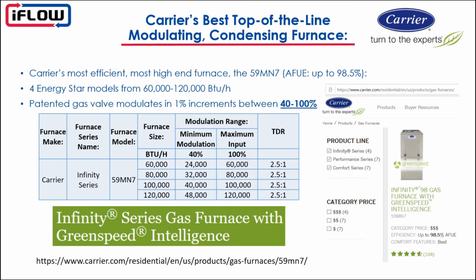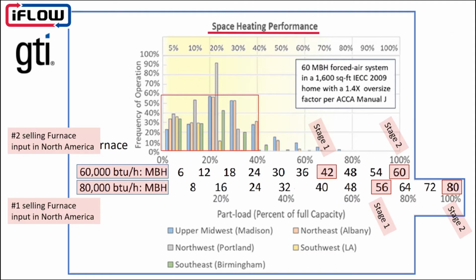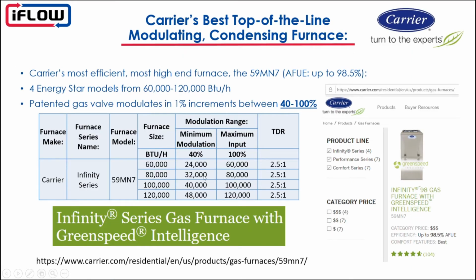The question, I guess, here is, how would this unit modulate based on the distribution that we saw on the previous slide, when we see that most of the heating is below 24,000 BTUs. So in this range, from 0 to 24,000 BTUs, unfortunately, even that newest furnace would not be able to modulate. It modulates from 24,000 upward to 60, but doesn't modulate below that, as far as I can tell from the information provided by Carrier on its website and through its brochure.